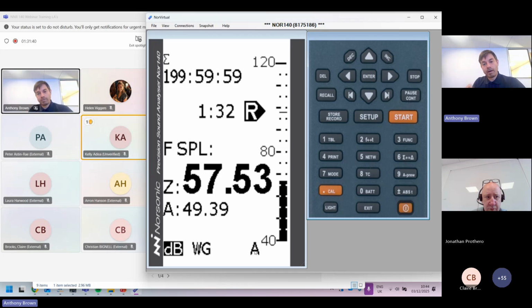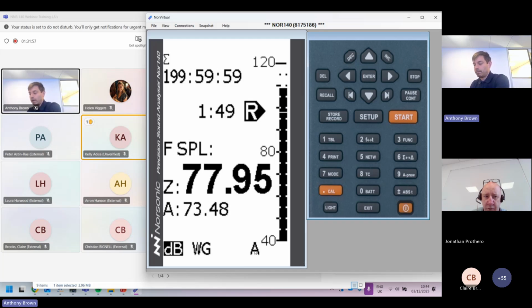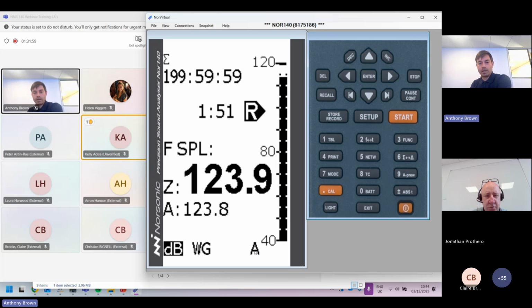And now I've got a bit of a reference sound level. Really, I want the microphone and the whole kit just set up in the place it's supposed to be on the floor. So when I'm talking, it's a bit more representative of the room. Some people may place the calibrator on the end of the microphone at the same time, just to get a read in and to show that they did calibrate it. This is down to your internal procedure. It also just shows that the microphone was working in your case. So that's good evidence.